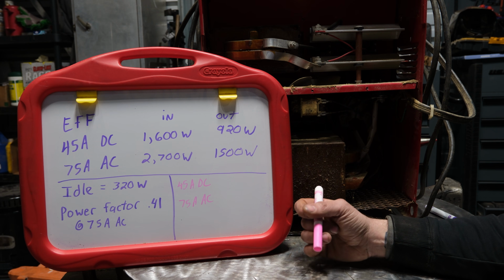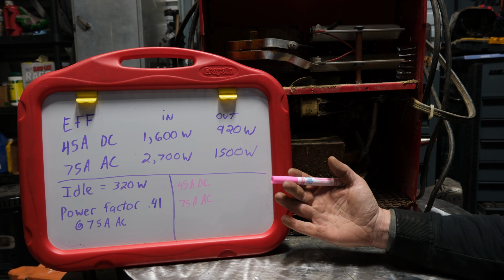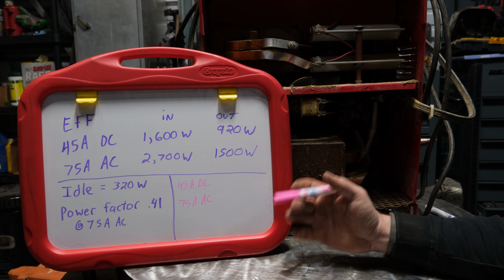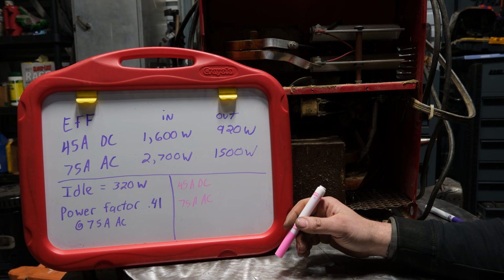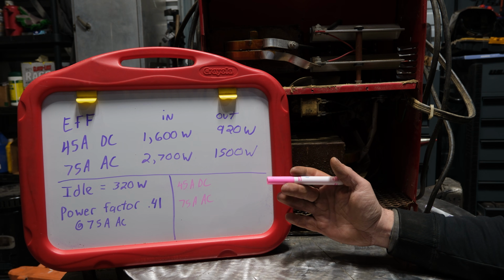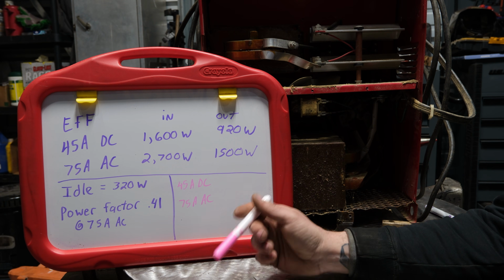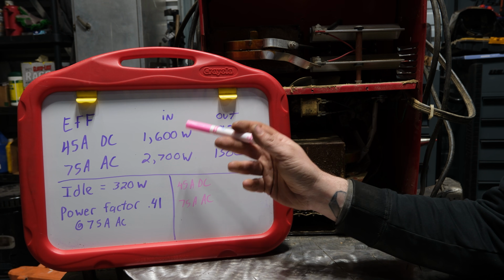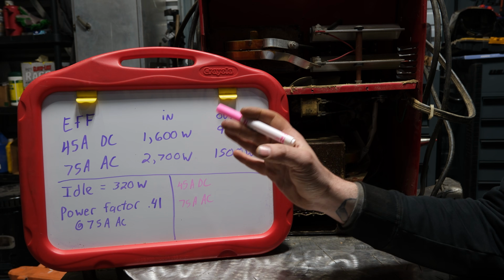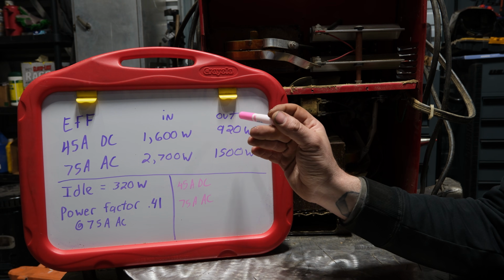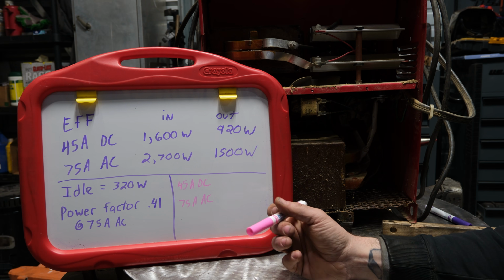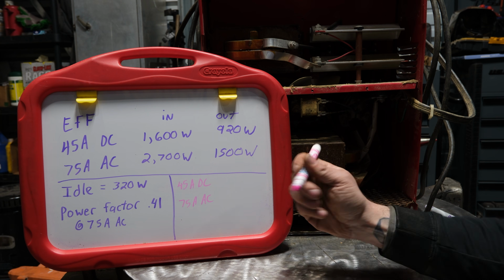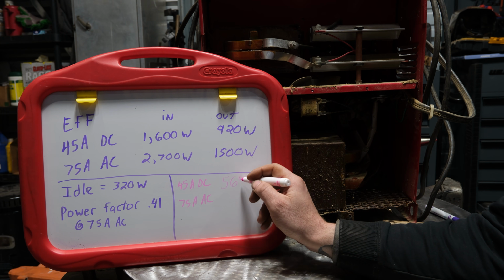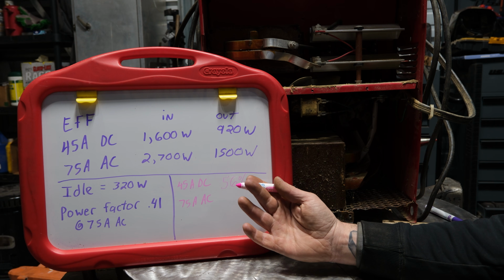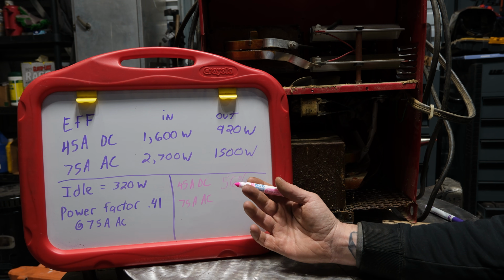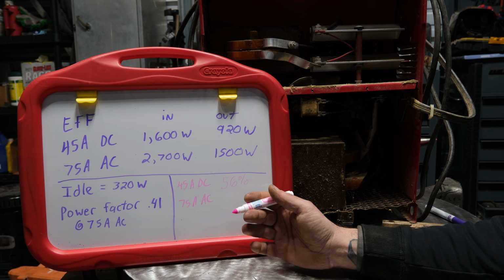So the moment of truth, the moment all of you guys have been waiting for, and that is exactly how efficient, or inefficient, this bastard is. I ran all of the numbers and came up with some answers, and it's not too surprising. First off, at 45 amps DC, so with it in DC mode, it consumed 1,600 actual watts, and that is corrected for the power factor, and the output was 920 watts. So that would put it at about 56% efficient, which is absolutely abysmal, but not really too unexpected. Any of these older transformer machines, if you can hit above 50% at taking input power and converting it to output, you're doing pretty good.